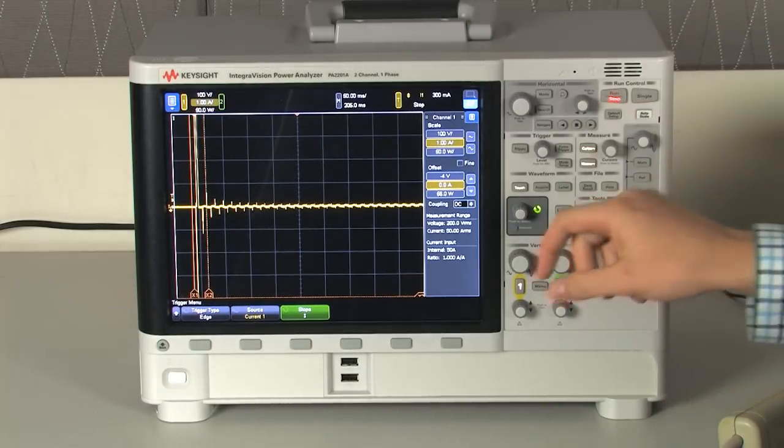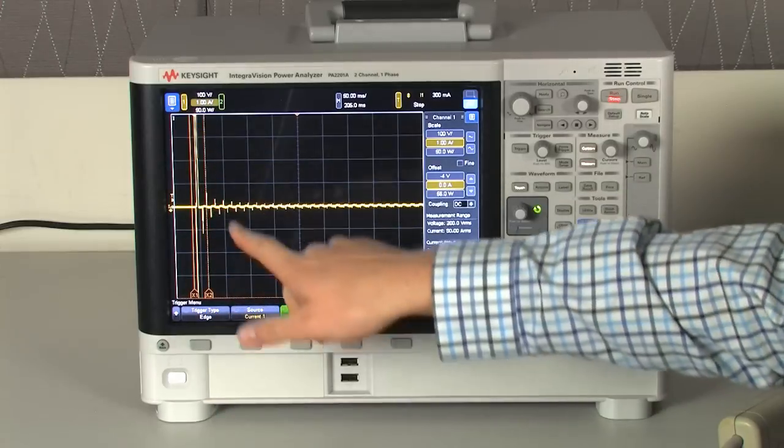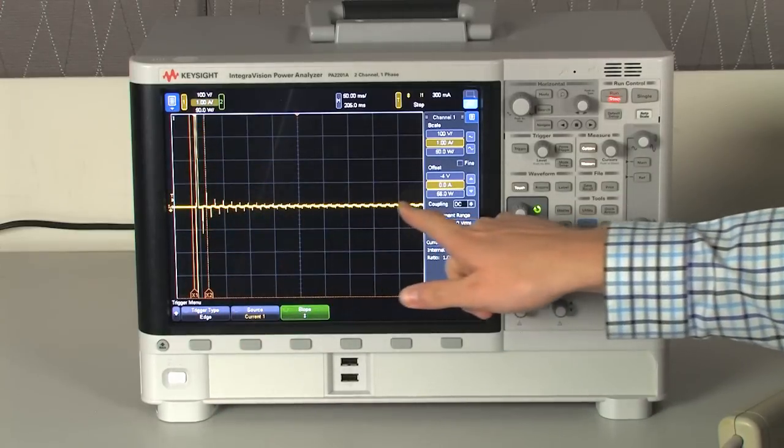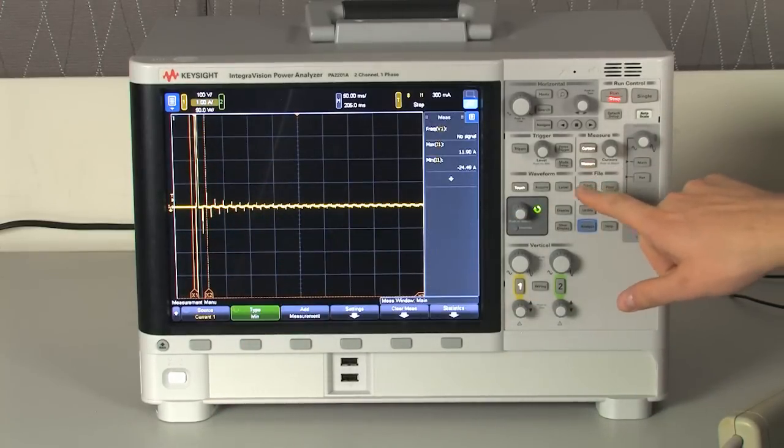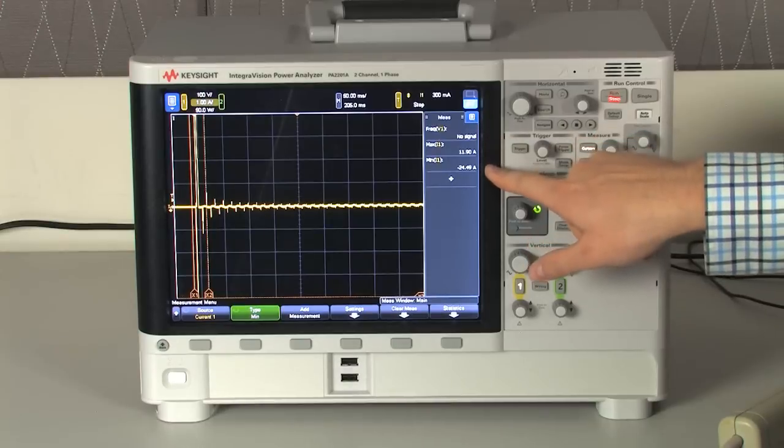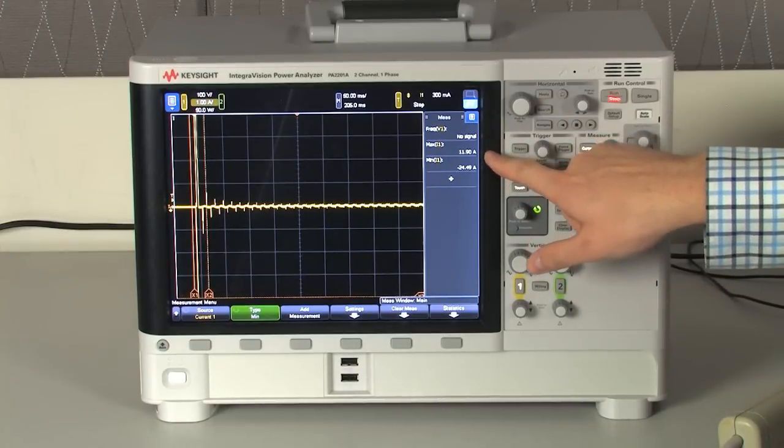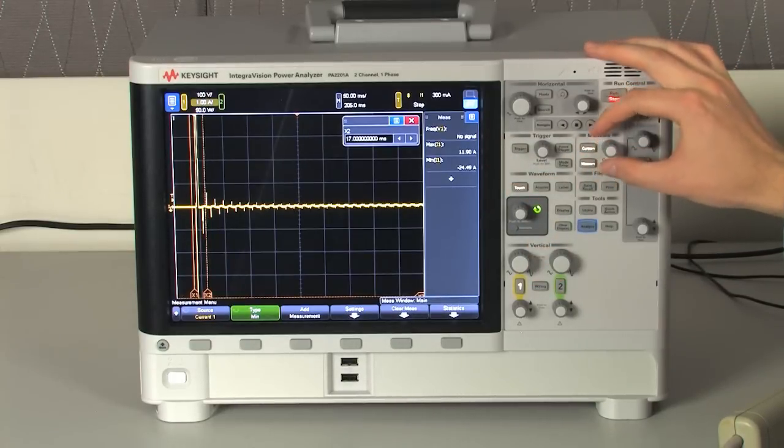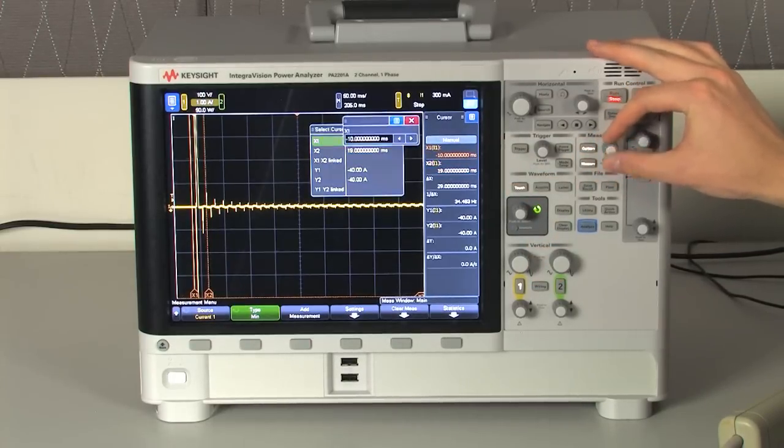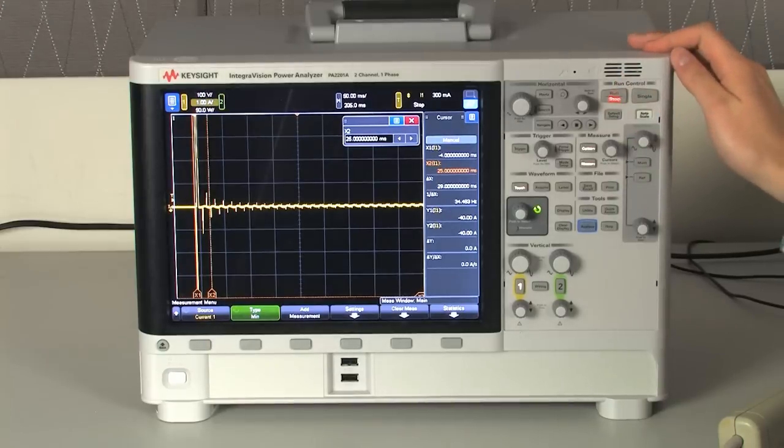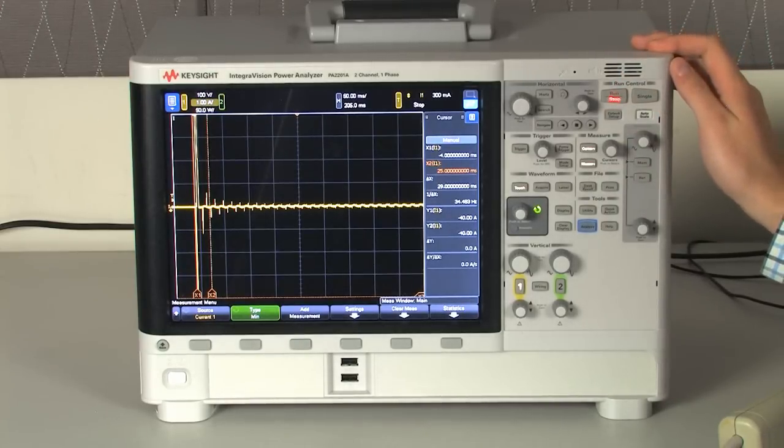There we go. So now we can see we had a huge inrush current and then gradually went down to steady state. If I go into the measure menu I can see what the peak of the inrush current was and I can use the cursors to measure the time of the inrush current event. As you can see the scope-like features of this power analyzer make it very easy to measure inrush current.